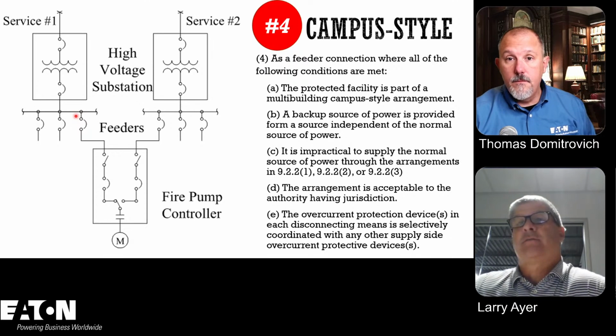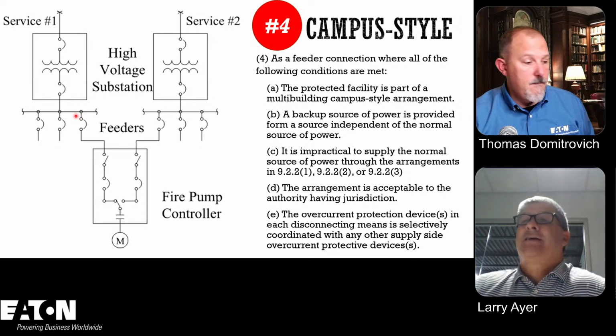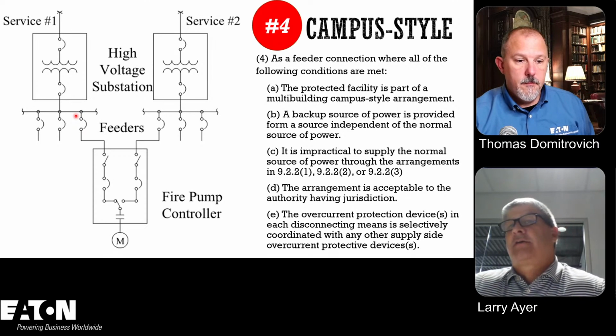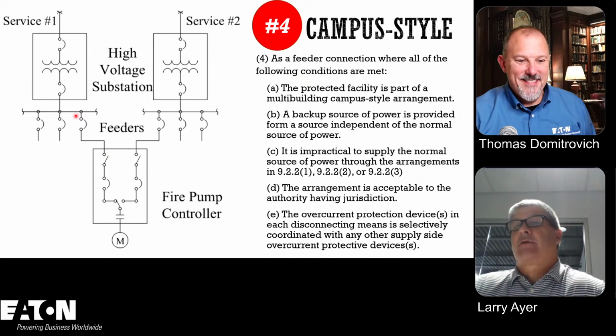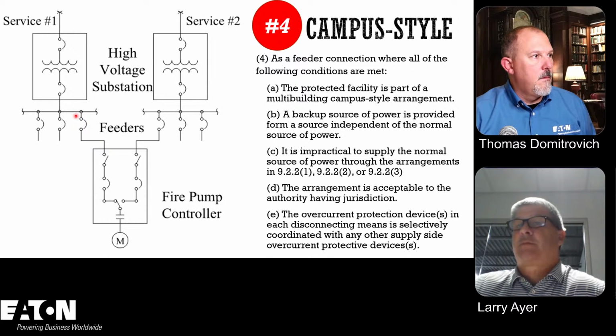That's correct. So this is a little more complex. When you do have campus styles, these are basically having feeds coming from buildings, so they're not really service conductors. They come from some medium voltage setup, and then they have an overcurrent protection device, and then they become feeders. So number 4 strictly talks about feeder connections, and providing backup sources of power. If you have a feeder from a campus style, you really want to have a backup generator or backup source of power. That could be 2 feeders. So there are other ways to do it on a campus style.